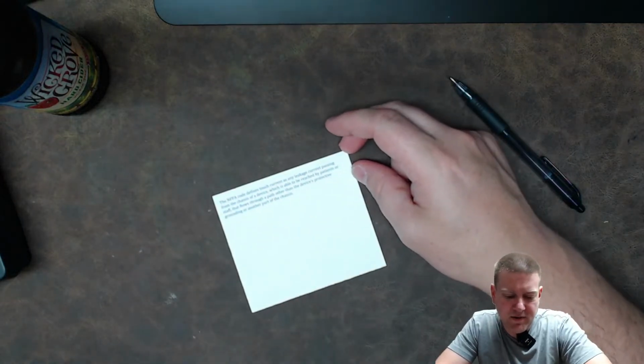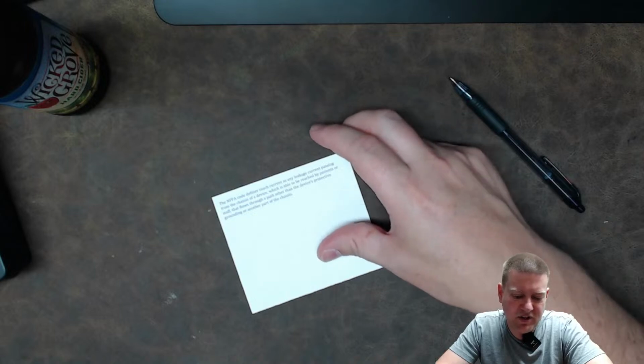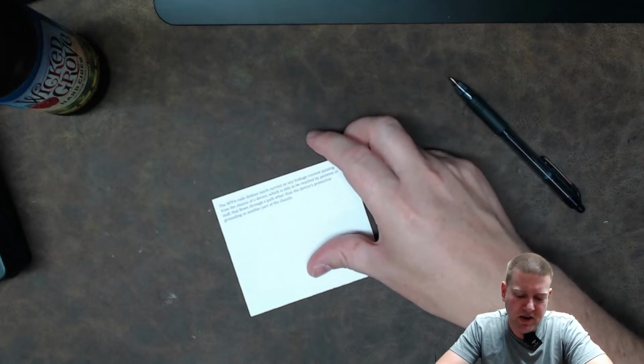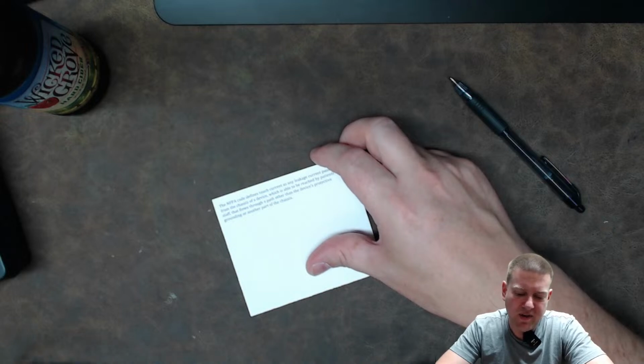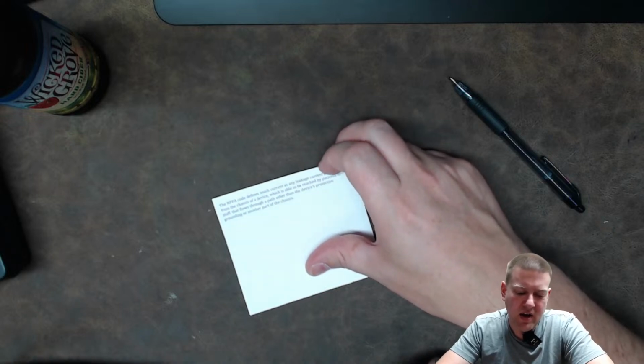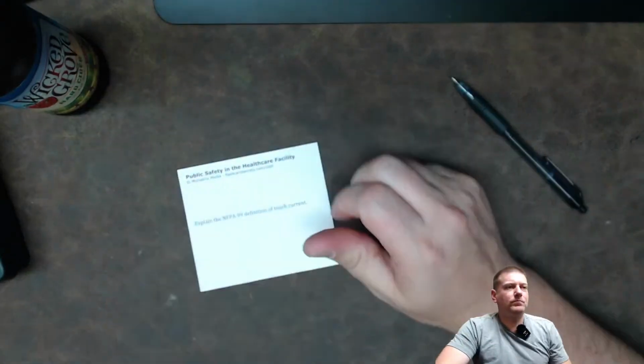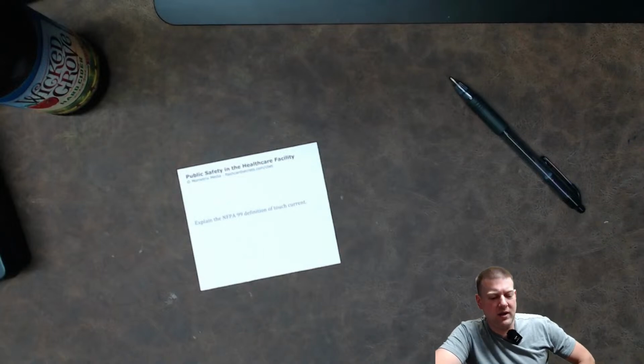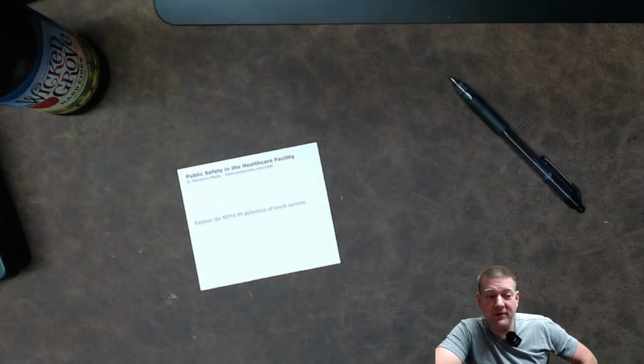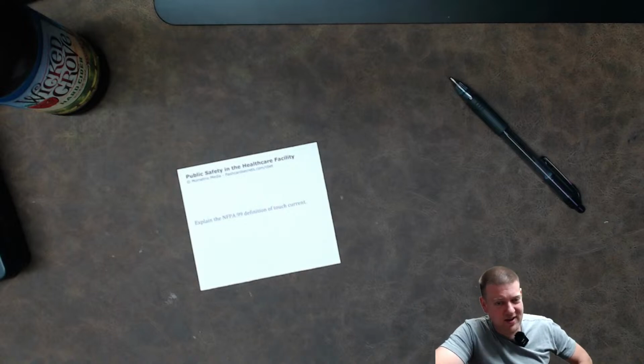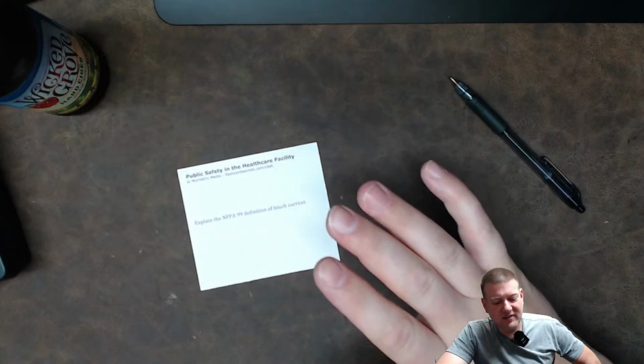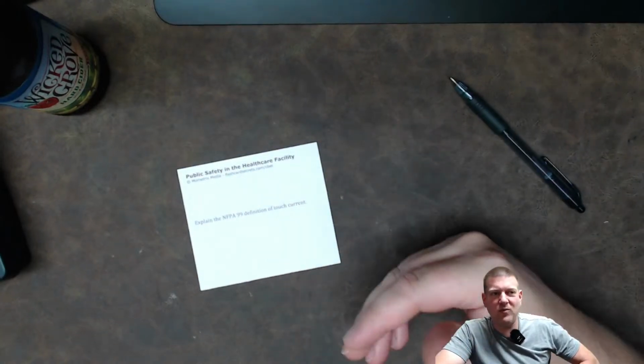NFPA code defines touch current as any leakage current passing from the chassis of a device, which is able to be reached by patients or staff, that flows through a path other than the device's protective grounding and other parts of the chassis. This is the number one reason why on electrical safeties we check ohms first for the ground conductor, because if you have a faulty ground conductor, you're also going to have a faulty leakage reading. We always test the ground conductor first, because if that fails, why even continue with leakage?